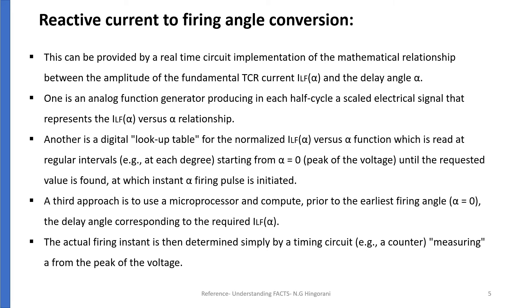There are two other approaches. The second is a lookup table for normalized ILF of alpha versus alpha function, which is read at regular intervals starting from alpha equal to zero until the requested value is found, at which instant the alpha firing pulse is initiated. The third approach is to use a microprocessor to compute, prior to the earliest firing angle, the delay angle corresponding to the required ILF of alpha. The actual firing instant is then determined simply by a timing circuit measuring from the peak of the voltage.